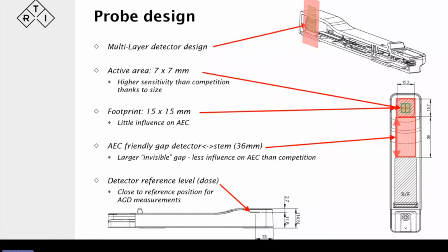The reference level for dose is indicated. You saw it here. Maybe you can make it out, but that's a small white line. That's at 2.7 millimeters from the surface of the probe, and that's where the reference level for dose is. It's quite interesting to have it there because it gives some benefits when, for instance, measuring for the AGD, where we want to look at the skin dose or the glandular dose, and we want to be as close as possible to the paddle. So with the mammo probe, we can basically just tape it to the underside and have a very well-defined dose reading close to the paddle, which is where the skin is, of course.